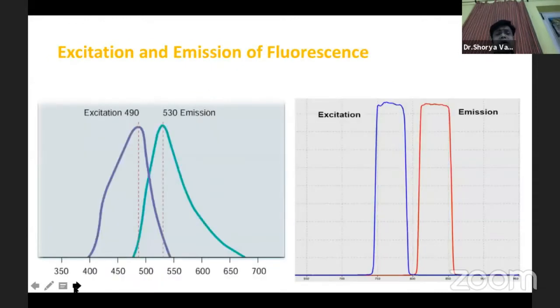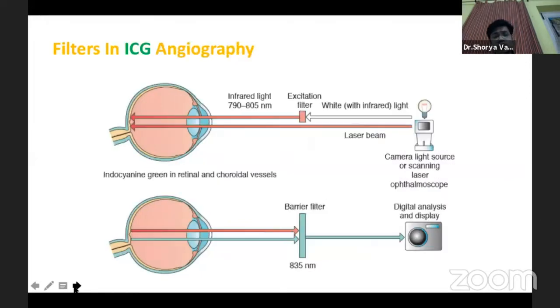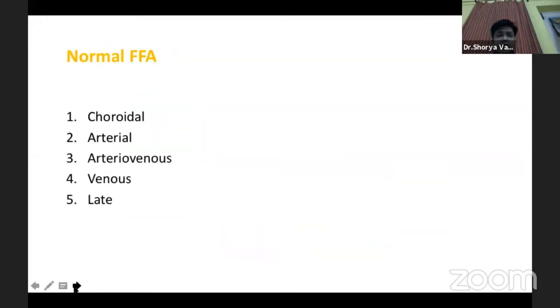The excitation and emission curves for fluorescein are 490 nm excitation and 530 nm emission, and for ICG they are 790 to 805 nm excitation and 835 nm emission. These correspond to the filters that we use in the procedure for both ICG and FFA.